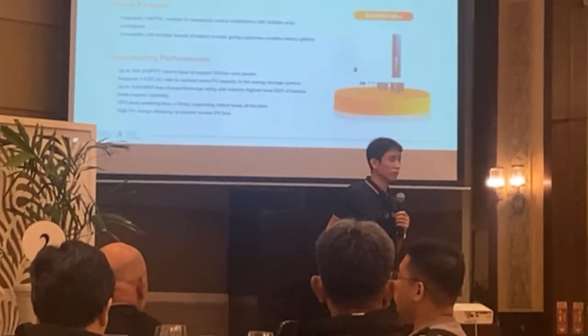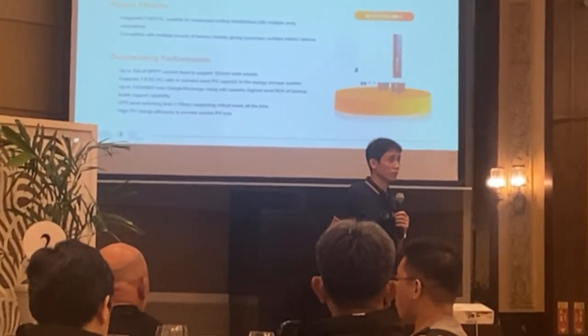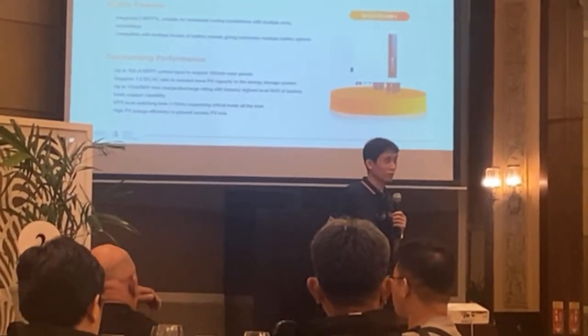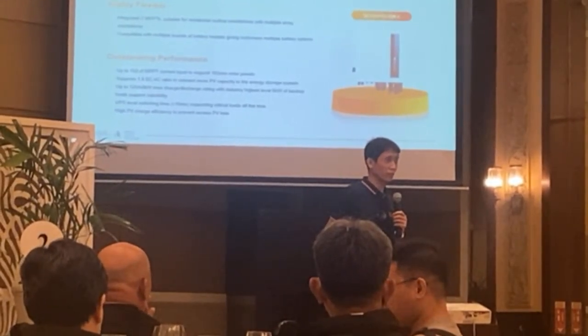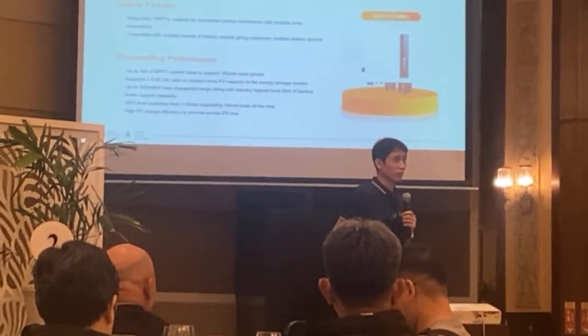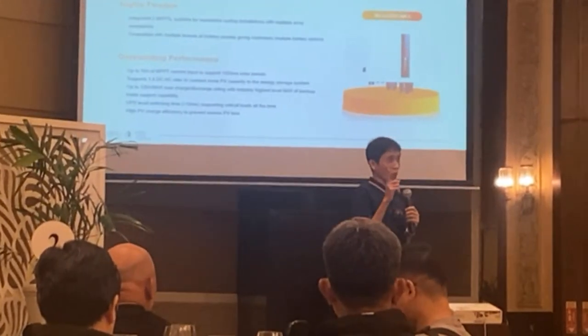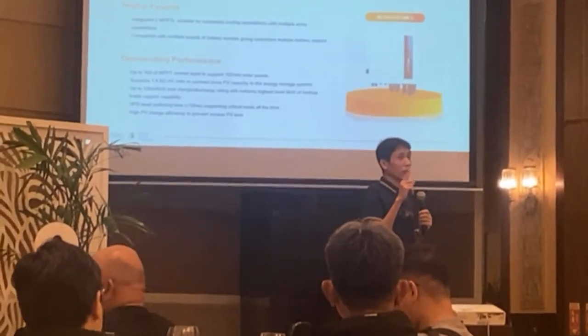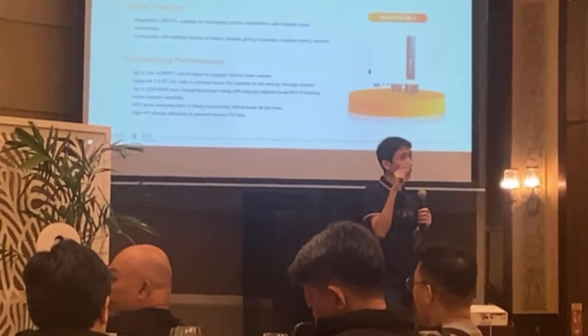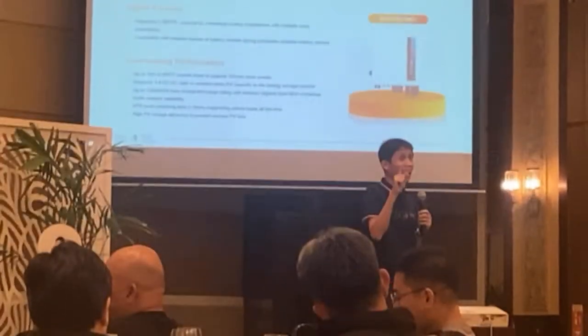Is it correct that what needs to be matched is the CT sensor and the meter? Correct. But as far as the inverter is concerned, I can interchange the Acrel and the Eastron without any changes in the setting. It's supposed to work that way. Okay. Because remember, the communication is between meter and inverter. So the ratio is within the meter and the CT. Okay.